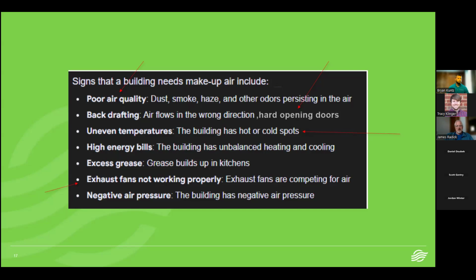Excessive grease, this is for kitchens. Everyone's familiar with that. Exhaust fans not working properly. The more exhaust you put on a room, the more negative it gets. It's like a Coke bottle with multiple straws in it, pulling on that and you don't have a way for air to come in, it just keeps getting worse and worse. And actually the performance of every one of the exhaust fans competing for air goes down. And of course, I talked about the negative pressure.